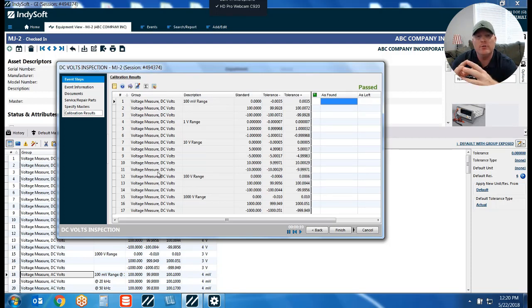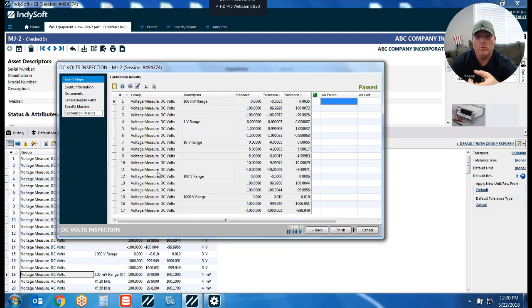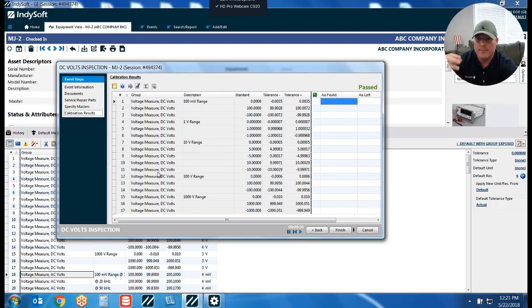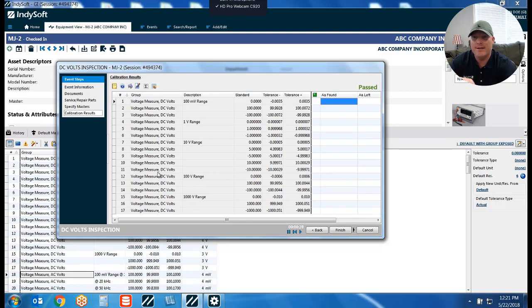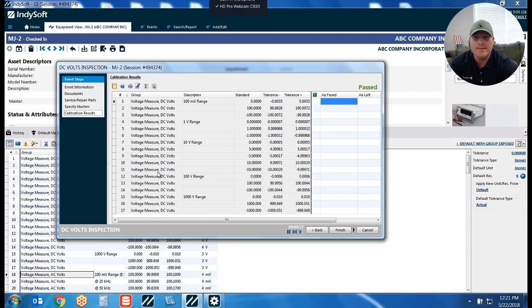So there are two things you can do with test point groups. One is you can create an option where your user selects which group of test points they want — that's the torque wrench example where it gave a pop-up asking for counter or clockwise measurement points. Or you can create an event and specifically say this group of test points applies to a particular event type — that's what I did with the AC and DC volts inspection events.